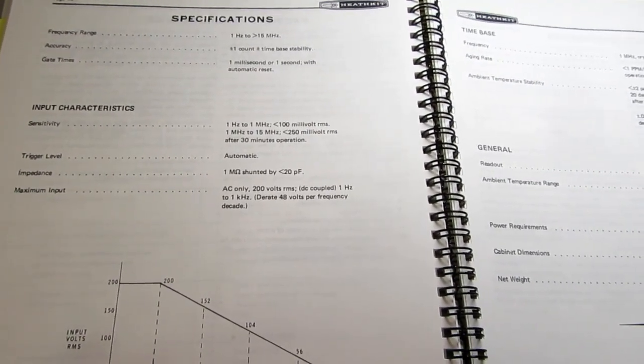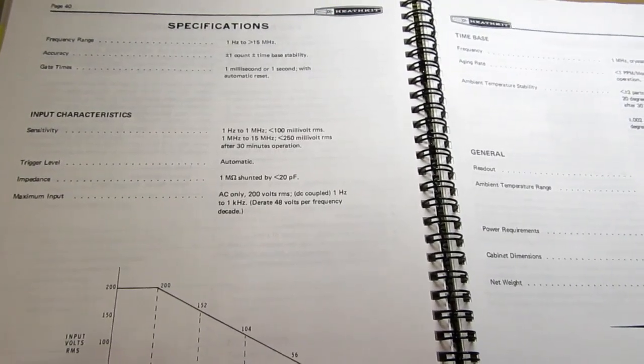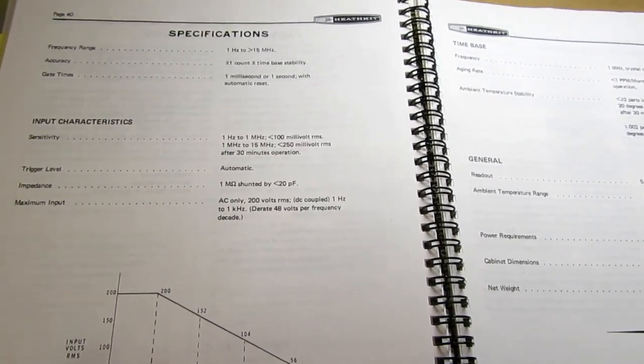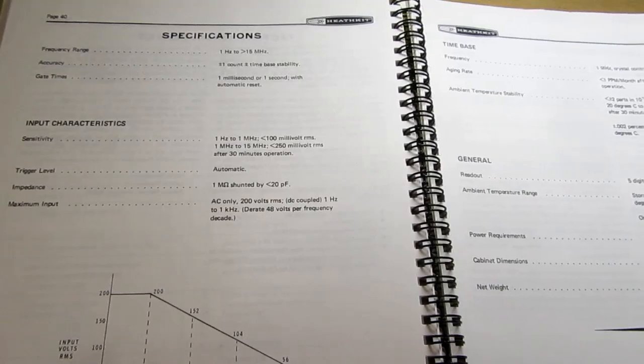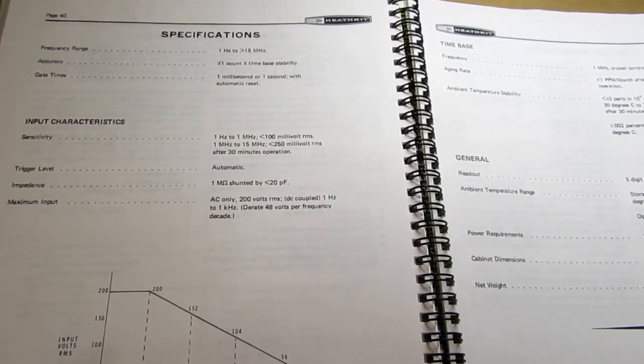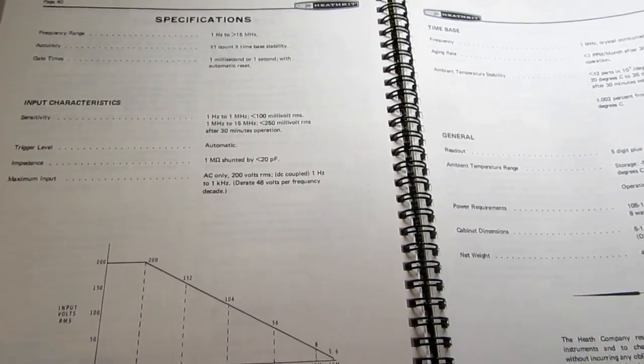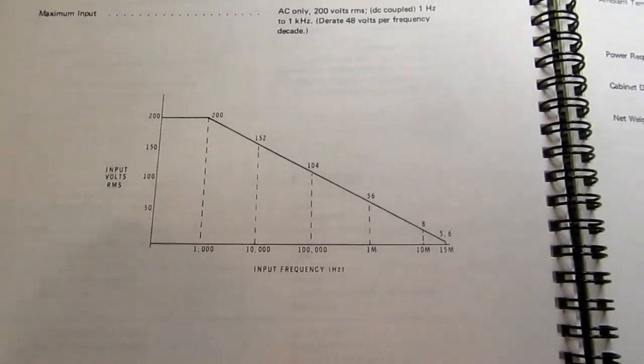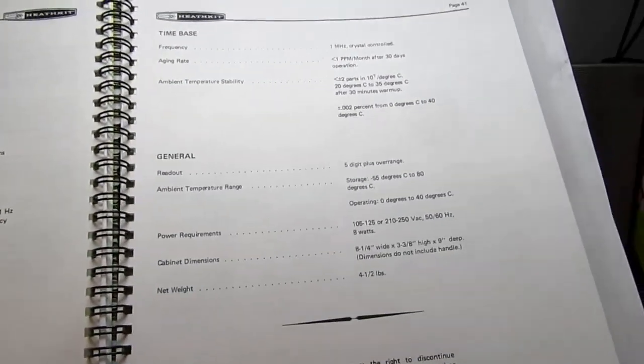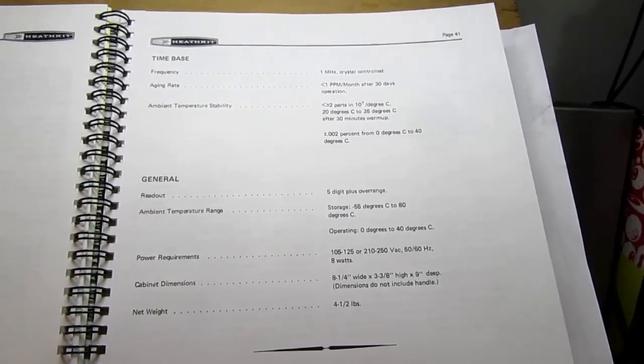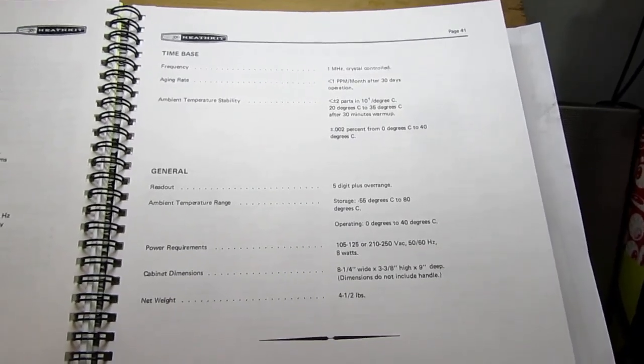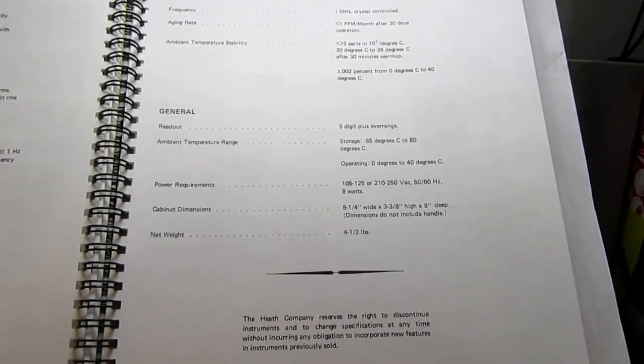Maximum input is AC only, 200 volts RMS, 1 Hertz to 1 kilohertz. Derate at 48 volts per frequency decade, and there's a chart illustrating that. Frequency of the time base is 1 megahertz crystal controlled. All the other stuff we already knew.